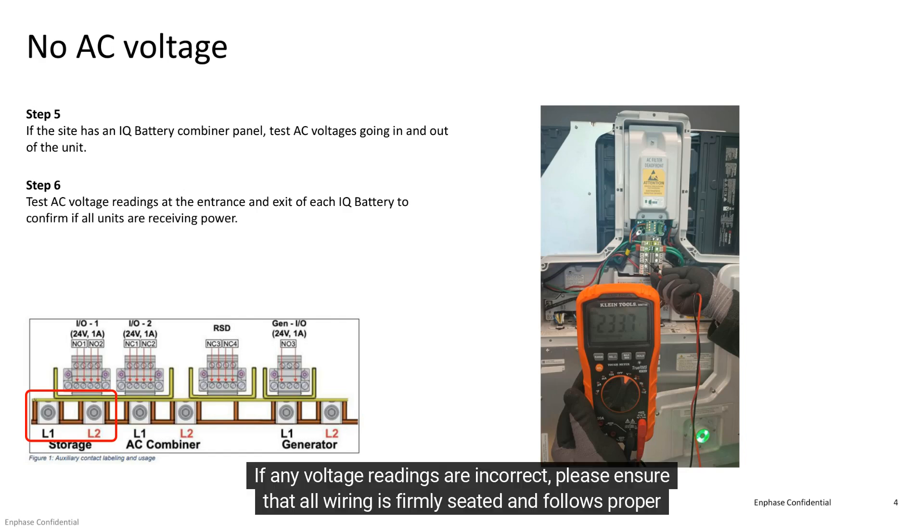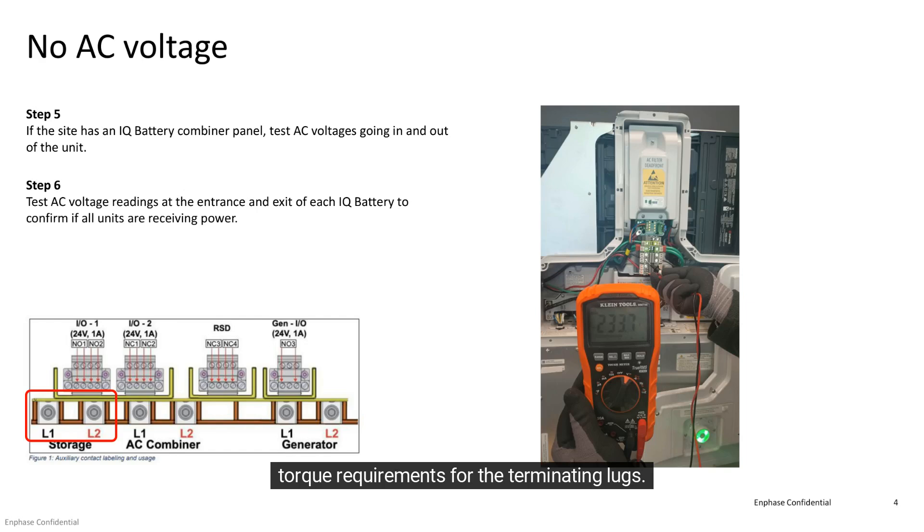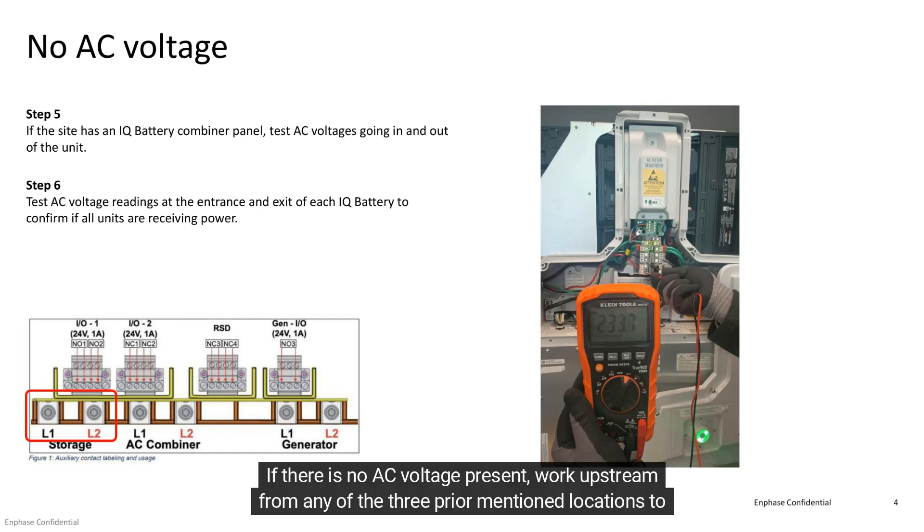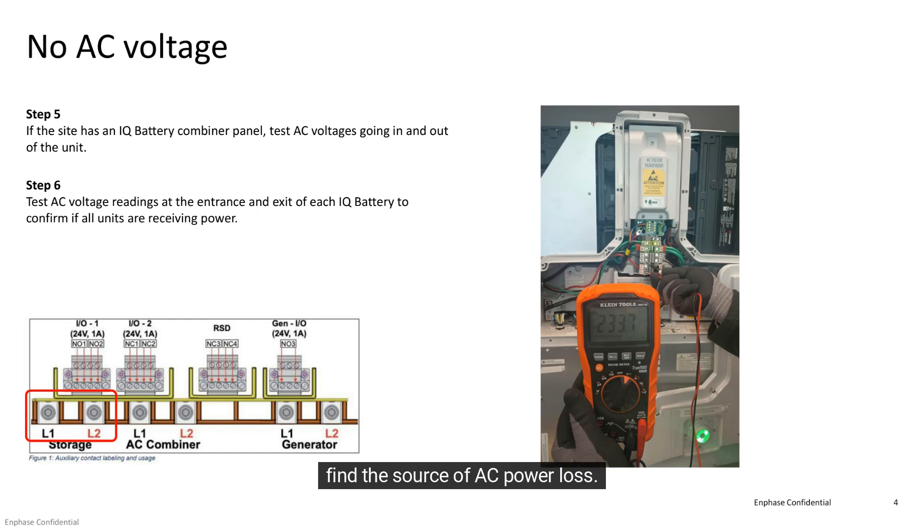If any voltage readings are incorrect, please ensure that all wiring is firmly seated and follows proper torque requirements for the terminating lugs. If there is no AC voltage present, work upstream from any of the three prior mentioned locations to find the source of AC power loss.